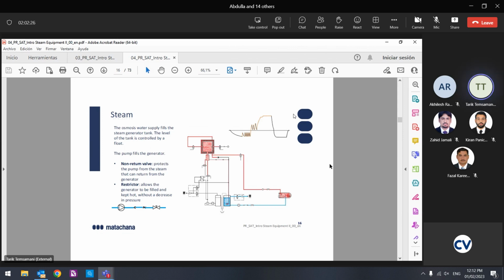This valve is always open and closed, not because there is condensate here always. So if it is a steam issue, I can check this non-return valve, the regulator, and the solenoid valve for opening. These are the paths which are available. Now I will ask a different question concerning the steam. For example, the steam in the chamber never reaches my pressure to start the sterilization. What can be the problem?